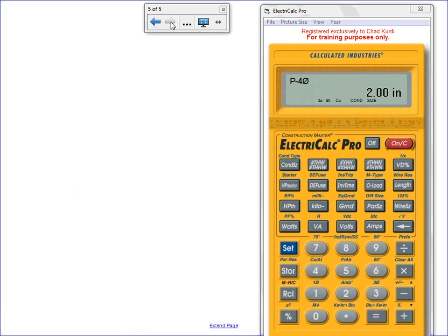Number 5. Let's go to question number 5 for A, guys. I have 8 conductors, hot, number 12, installed at an ambient temperature of 100 Fahrenheit. Find how many amps you can pull out of this baby. That was easy, piece of cake.